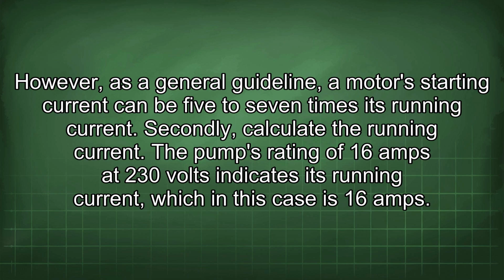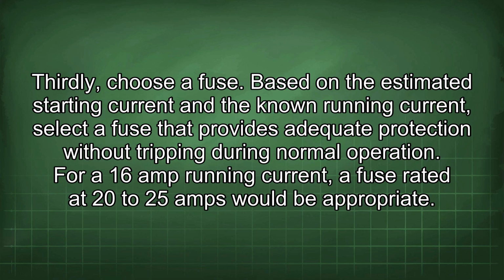Secondly, calculate the running current. The pump's rating of 16 amps at 230 volts indicates its running current, which in this case is 16 amps. Thirdly, choose a fuse. Based on the estimated starting current and the known running current, select a fuse that provides adequate protection without tripping during normal operation. For a 16 amp running current, a fuse rated at 20 to 25 amps would be appropriate.